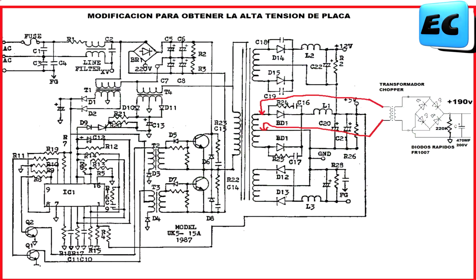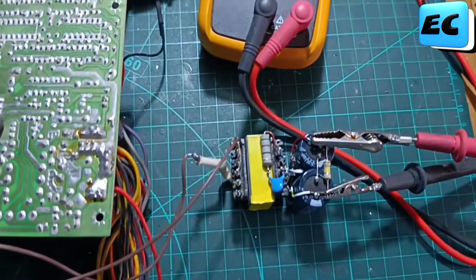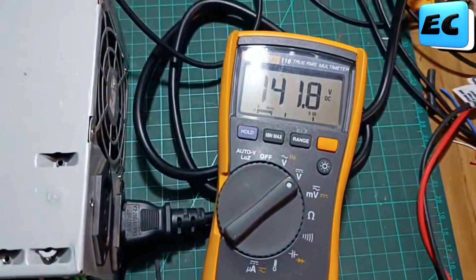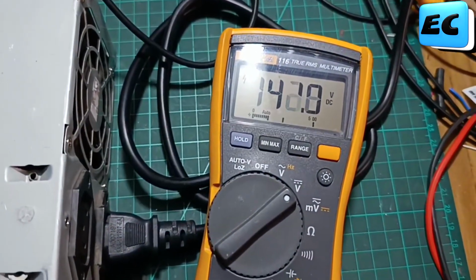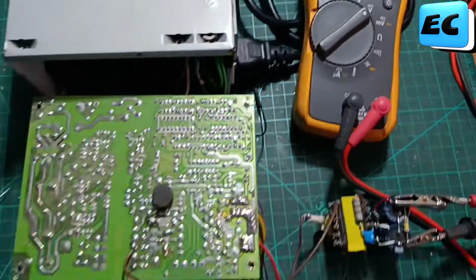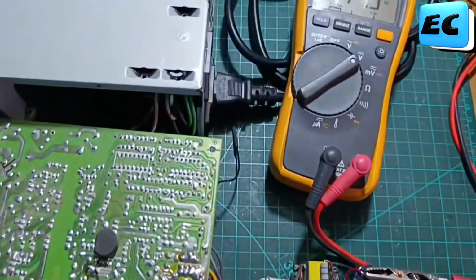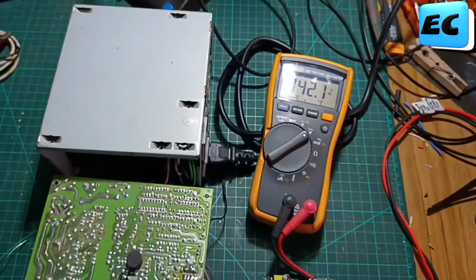From the cold side, let's say the side that goes to the low voltages, we will test with a multimeter, plug in the power supply, of course, and measure the voltage that is rectified in the auxiliary chopper. For example, with the cable connected to this first point, here I have 142 volts.